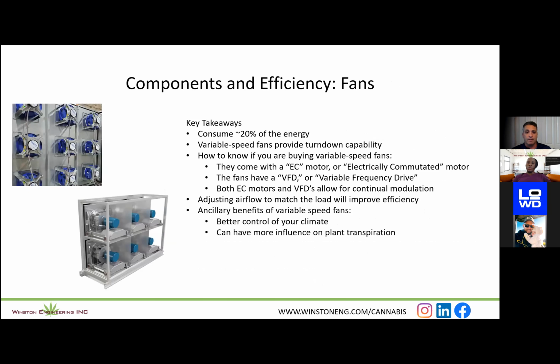So fans really make up, I say the other 20%, but the majority of the remaining energy hit that you get from your equipment. And just like in compressors, you want to have the ability to turn down or have variable speed fans, right? Now, in many situations in this industry, you're going to have constant airflow in your space. So you're not necessarily going to be varying the airflow every minute in your space. But again, if you happen to be at 50% capacity, you don't need 100% of the airflow necessarily. So having that ability to ramp it down is going to be important in terms of efficiency.